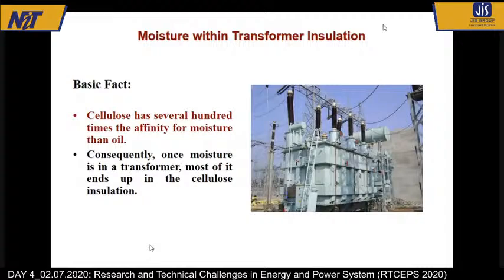Now if you take the case of a transformer, as I said, moisture will be generated inside this transformer. But then where will this moisture go? By the way, when we teach our students, we tell them that transformer oil is hygroscopic in nature. And when we say hygroscopic, we say that if you keep transformer oil exposed to atmospheric air, it will absorb moisture. But the unfortunate part is that the paper insulation, that means the cellulose, has an affinity for water 100 times more than oil. So inside this transformer, if there is moisture and two materials are trying to attract it, one is paper, one is oil, and paper's water affinity is 100 times higher, then it is quite obvious that most of the moisture will go to the paper insulation.